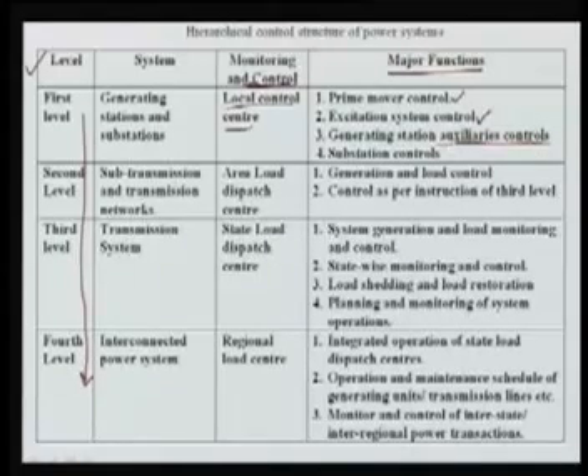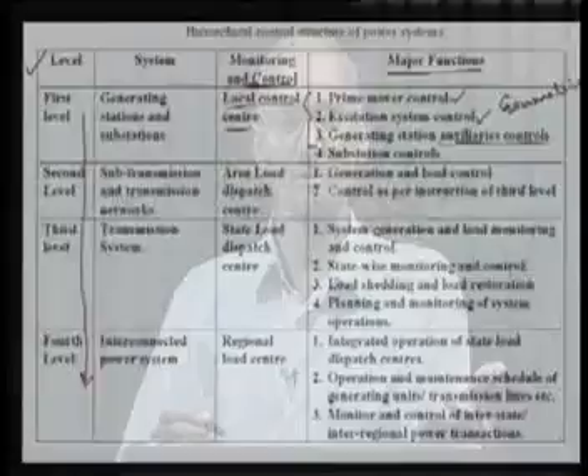So all these three, first 1 to 3, are related to your generating plant controls. Means you have to control the prime mover. What is the prime mover of your generating station? It is a turbine, and the turbine gets energy in terms of steam from your boiler. So we have to control, and here normally it is called the governor control. Governors are there, so they try to increase the output of the turbine, and finally it is coming to your alternator and it gives the output accordingly.